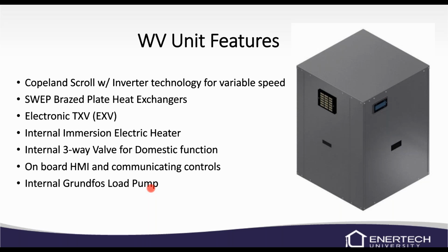It does have an onboard HMI. HMI stands for human machine interface, and it has the communicating controls. On that picture to the right, it's that box with a little bit of blue right in the middle of it, towards the top of the unit. That's the HMI. Again, there is an internal Grundfos load pump, factory installed, insulated inside the cabinet. It's up near the top back of the unit. Keep that in mind because if you ever have to replace that load pump, you will have to take the top off the unit. So you may want to give yourself some clearance on top of the unit.